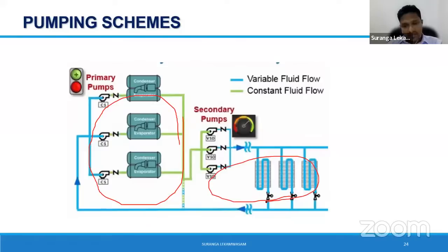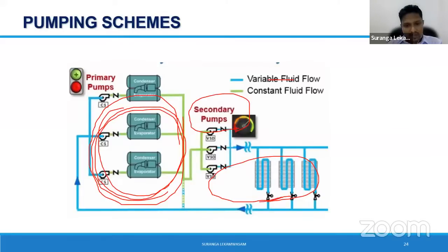Eventually, according to the load pattern, my demand varies. So my secondary pump must be a variable speed pump, right? But in this particular case, my primary pumps I have made constant speed pumps, right? So what will happen? In this loop I have a constant flow rate, whereas in this loop I have a varying flow rate.